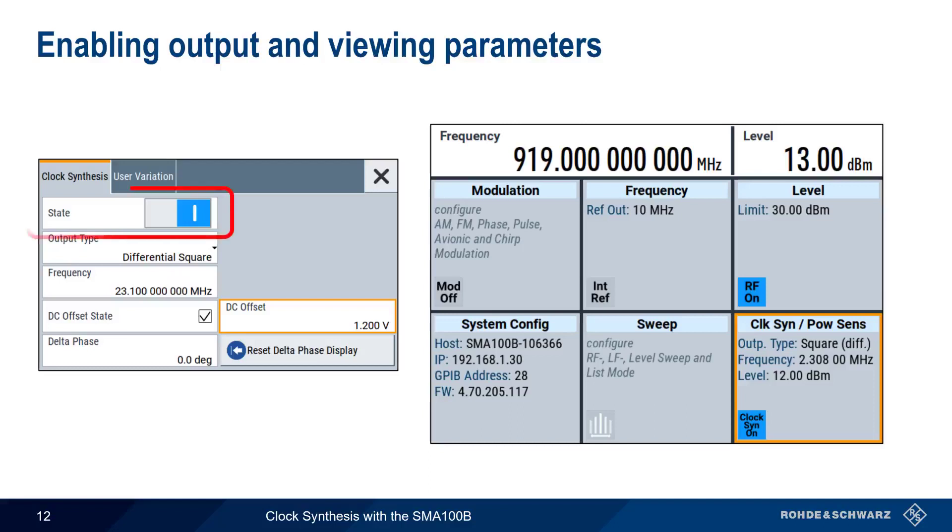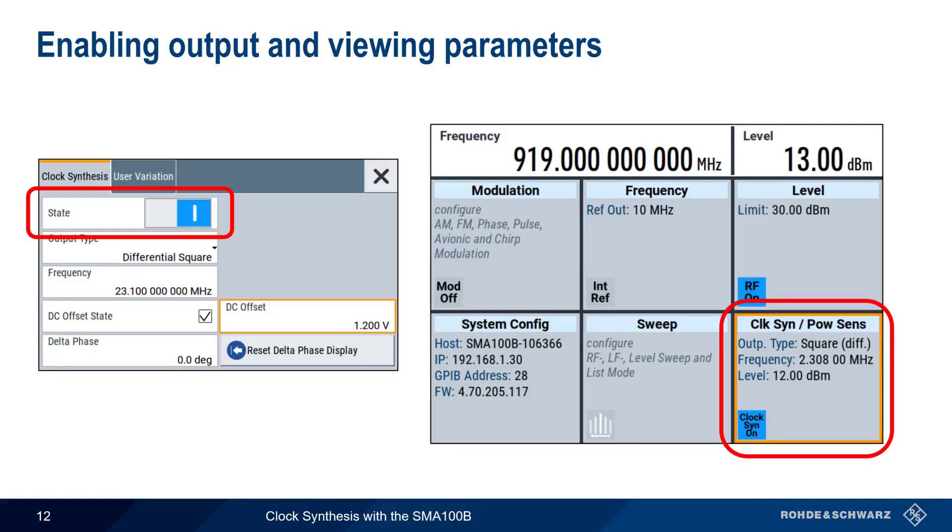The final step is enabling clock synthesis output by turning state to on. The clock synthesis tile on the main SMA100B GUI will display the state of clock synthesis, as well as output type, frequency, and level.